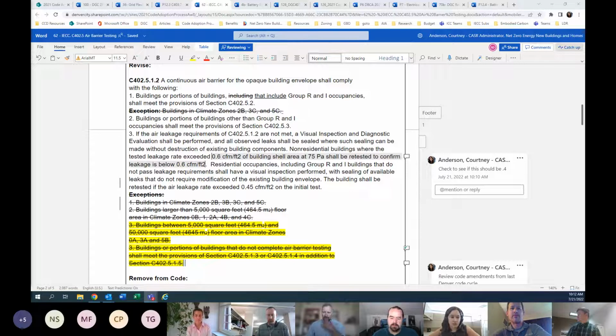Yeah, that's correct. To resolve this and move forward, acknowledging that this is the last supplemental hearing we have scheduled, it sounds like the group agrees it should be 0.4, with allowance for buildings that don't meet 0.4 to fix and get to 0.6, and then for John to verify the right language aligns with the 2021 IECC and the Denver Code amendments. I want to make sure I'm hearing all that right. Go ahead, Paul. I was going to say that matches my understanding, Courtney. Again, when it would come up for a vote, I would move that as something to vote on.